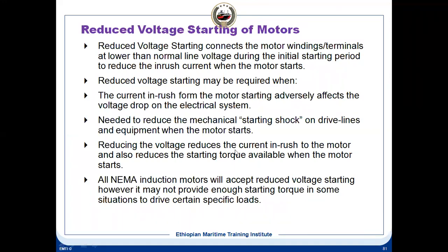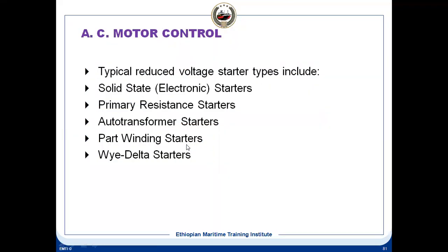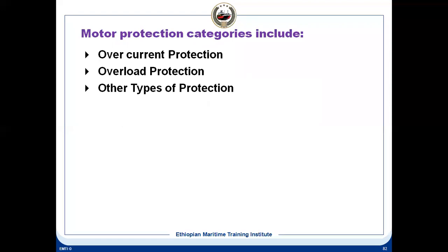Another reason is that reducing the voltage reduces the current inrush to the motor, and also reduces the starting torque available when the motor starts. NEMA, the National Electrical Manufacturers Association, says an induction motor will accept reduced voltage starting. However, it may not provide enough starting torque in some situations. So the starting torque will be less. For AC motor controls, we have seen various types of starting methods. Reduced voltage means solid state starters, electronic starters, primary resistance starters, auto transformer starters, part winding starters, and star delta starters. Let's see what the various protections available in the motor starter are.